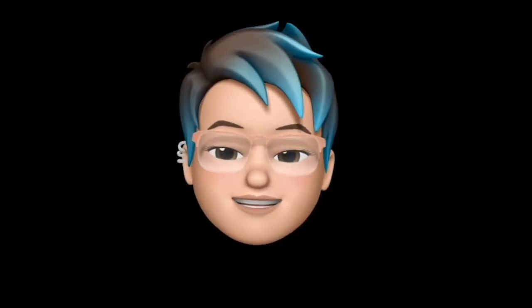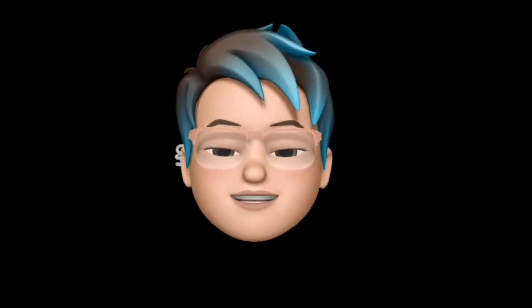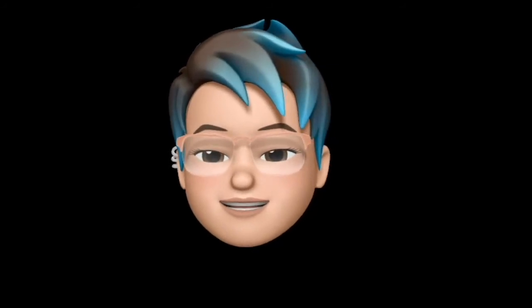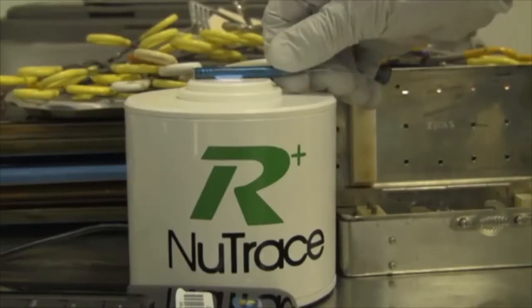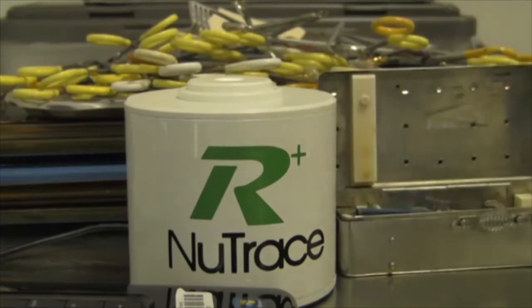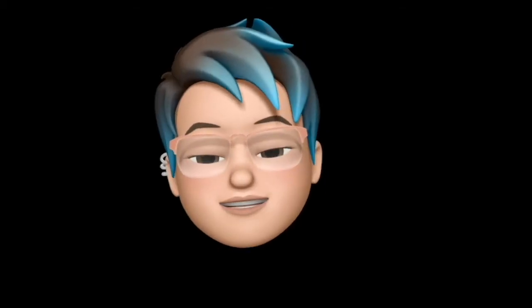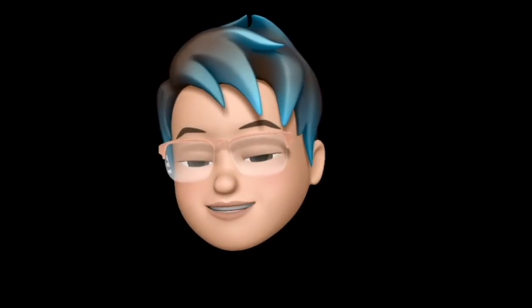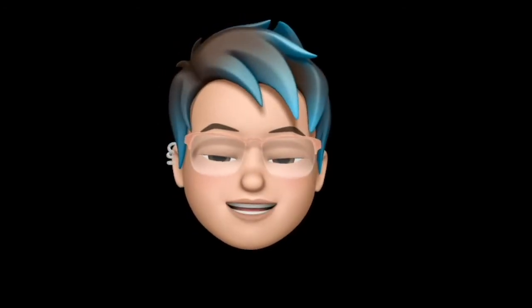As the code is laser etched into the surface of the instrument, it does not compromise the passivation layer and leaves the instrument smooth and intact. This extends the lifespan of the instrument considerably compared to the previously used scratching method. Instruments can be reprocessed easily over many years as the resulting marked surface still has its anti-corrosion layer.